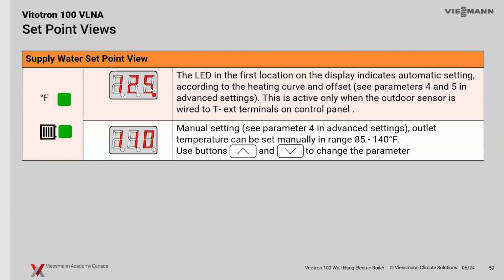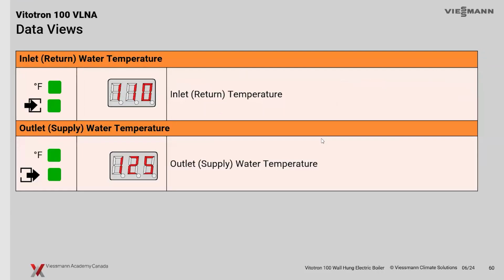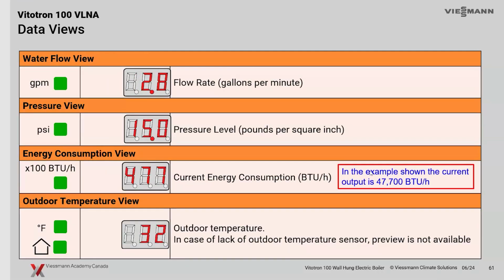If you're using the heating curve, it's a bit of a different setup. Again, if that little LED, that little dot right there is lit when you look at your temperature, then we know we're in outdoor reset. We're not in fixed supply temperature. And there's a little extra step you'll have to do to make your adjustments to your heating curve. We'll look at that in a second. And there's your supply in and your supply out, which we just talked about a little bit earlier.